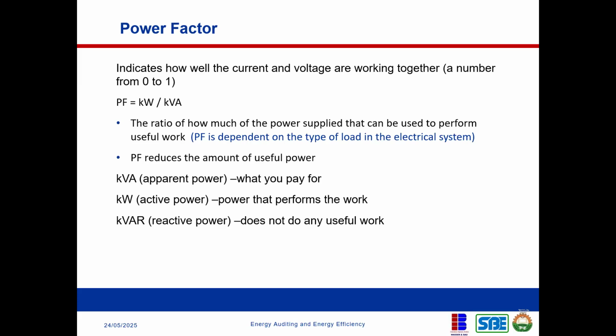So power factor equals kilowatt, which is your actual or real power, divided by your apparent power. We're going to explain in the next slide what real power and apparent power are, but just have in mind that to calculate power factor, it's your kilowatts, your real power, divided by your apparent power.